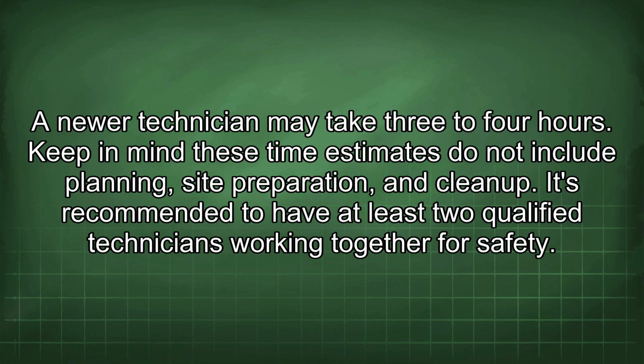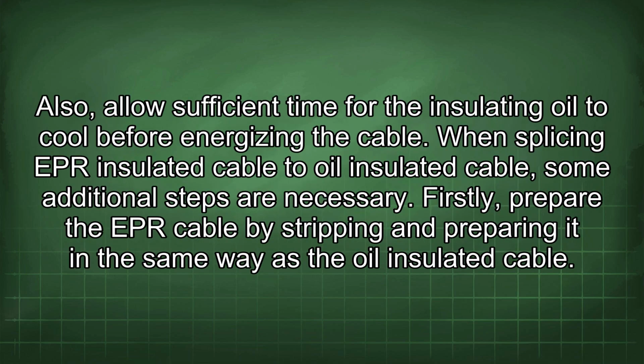Keep in mind these time estimates do not include planning, site preparation, and cleanup. It's recommended to have at least 2 qualified technicians working together for safety. Also, allow sufficient time for the insulating oil to cool before energizing the cable.